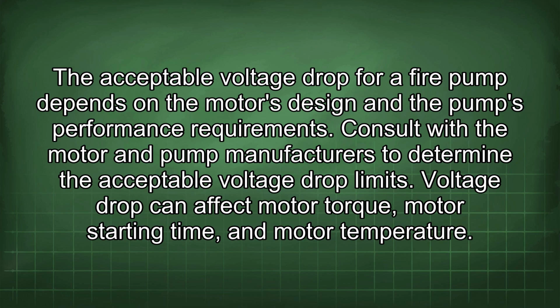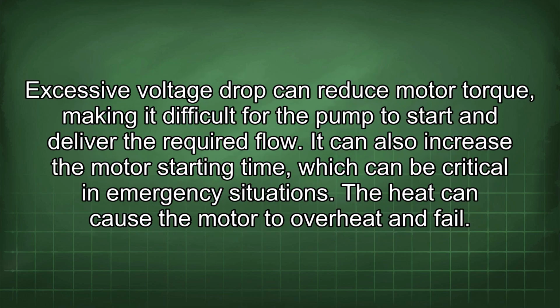The acceptable voltage drop for a fire pump depends on the motor's design and the pump's performance requirements. Consult with the motor and pump manufacturers to determine the acceptable voltage drop limits. Voltage drop can affect motor torque, motor starting time, and motor temperature. Excessive voltage drop can reduce motor torque, making it difficult for the pump to start and deliver the required flow. It can also increase the motor starting time, which can be critical in emergency situations. The heat can cause the motor to overheat and fail.